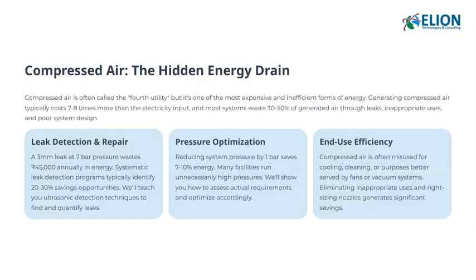Let's talk about compressed air, which is often called the fourth utility. But in reality, it's one of the most costly and inefficient energy sources we use. Generating compressed air can cost 7 to 8 times more than the electricity it consumes. And here's the surprising part. Most systems waste between 30 to 50% of the air they produce.